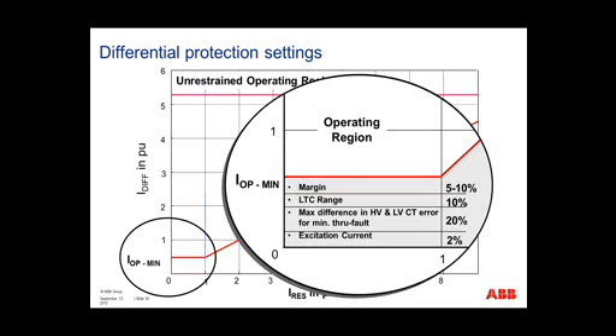Sources of errors are the load tap changer range, especially if you're not monitoring the position of the load tap changer. The differences in your high voltage and low voltage CT errors. For Class C, this is 10%. So on the high side, 10% plus the low side, 10% will give you 20% error. Excitation current offers a 2% error that we need to account for, plus a fudge factor, a margin of error of 5 to 10%.